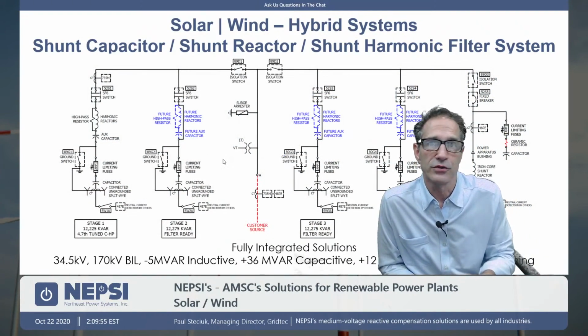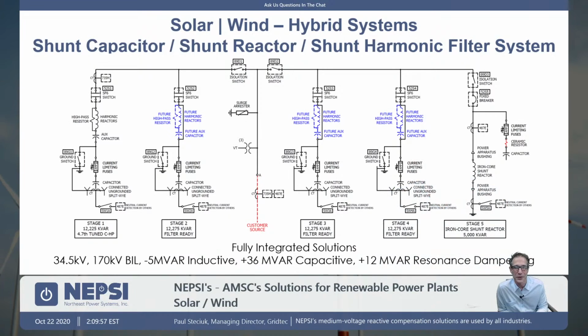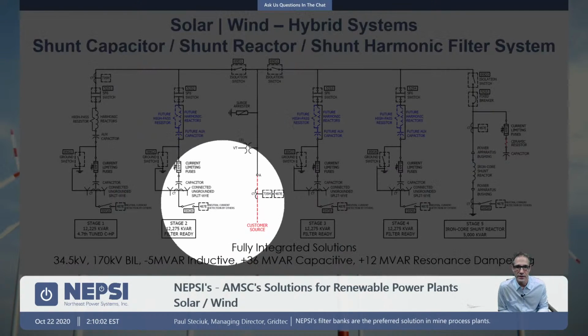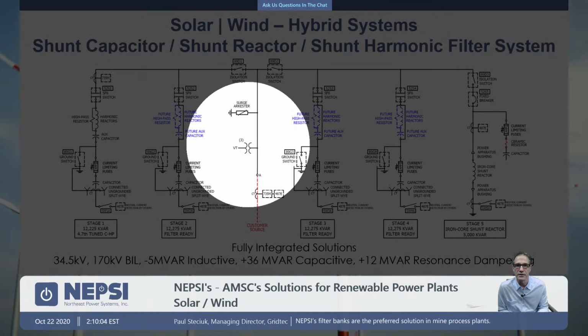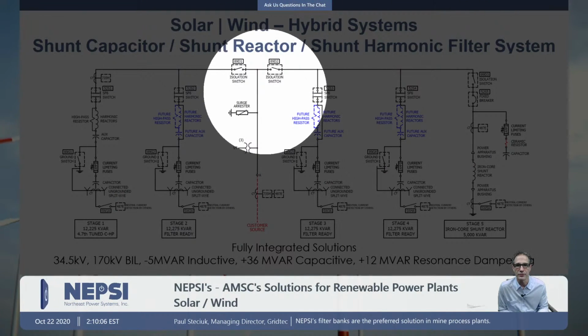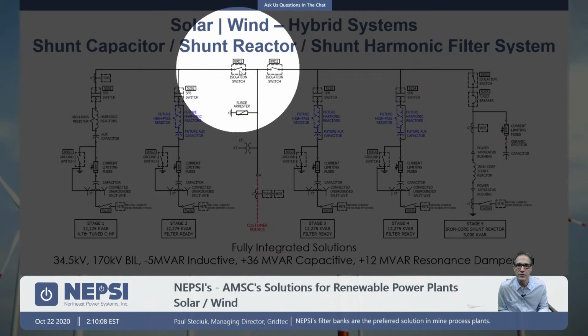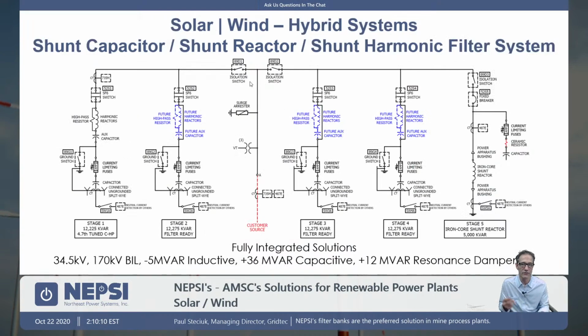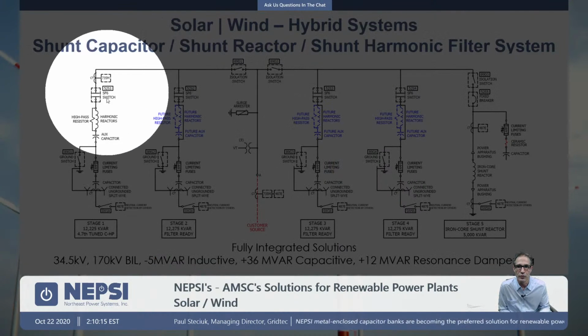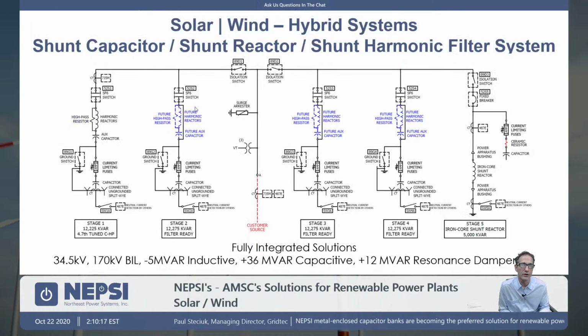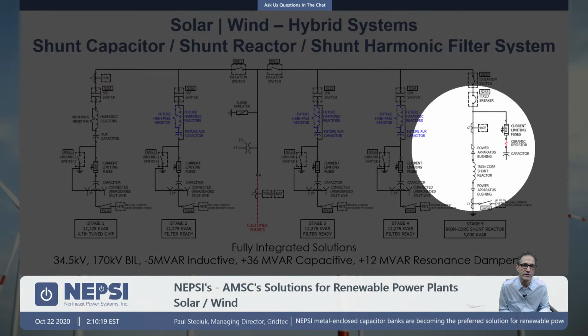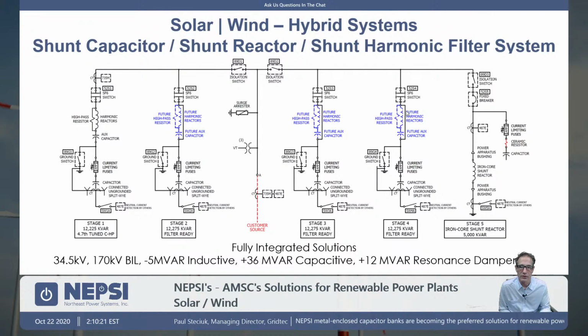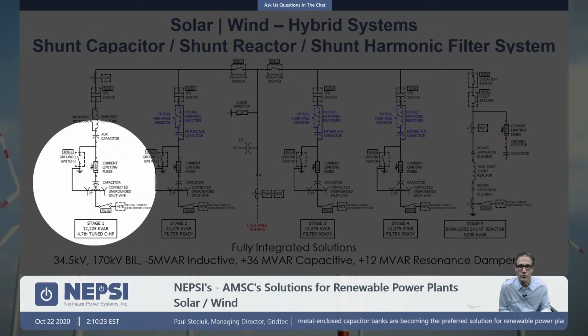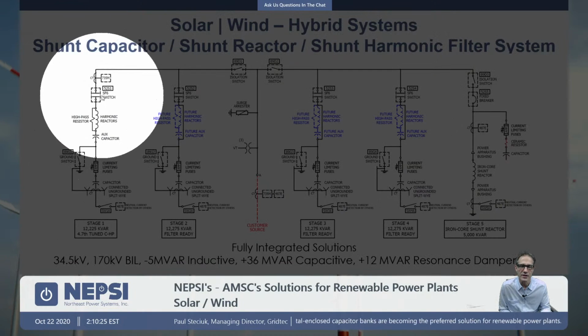So I want to show you a one-line diagram of that system. It's quite involved. We had an incoming area here, PTs and CTs on the incoming, lightning arresters. We had disconnect switches inside our equipment to provide isolation to allow for maintenance of the equipment inside. We can basically get into a portion of the equipment here, while the other portion, say over here, is in fact energized.